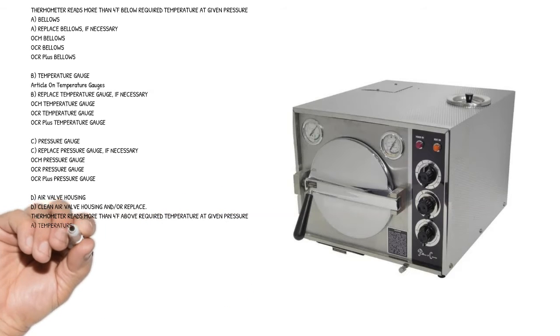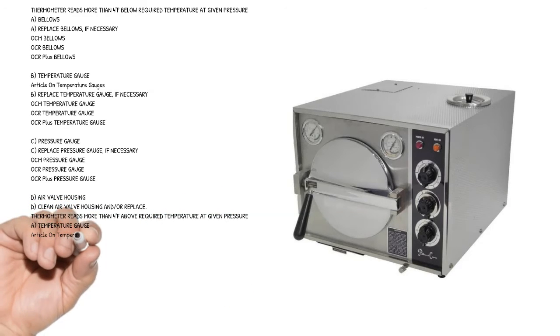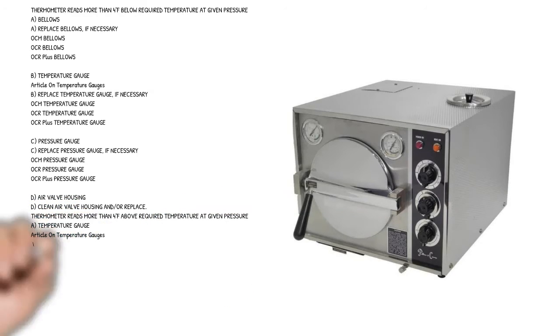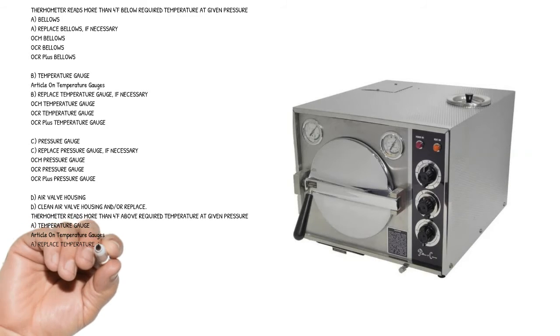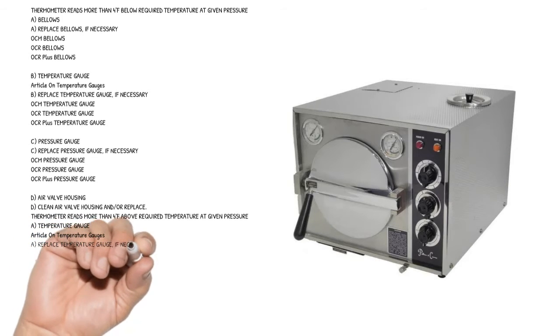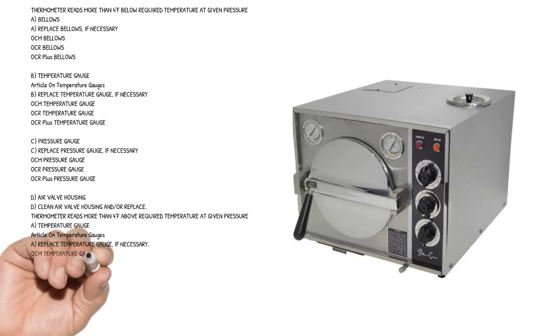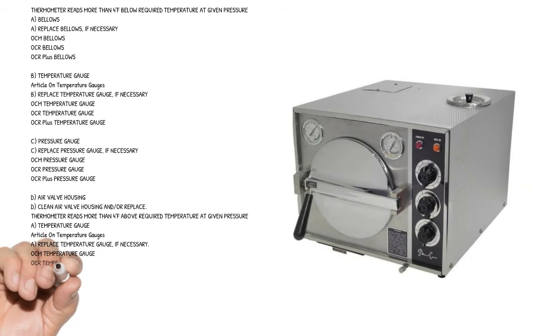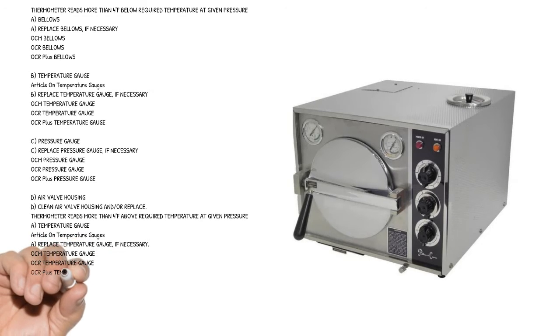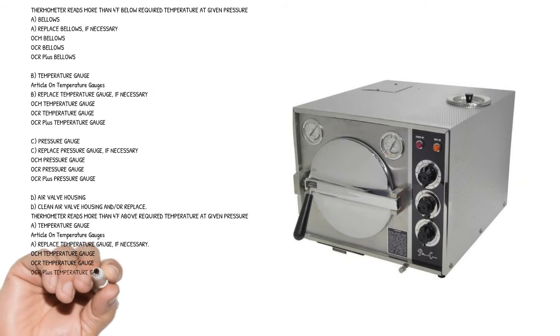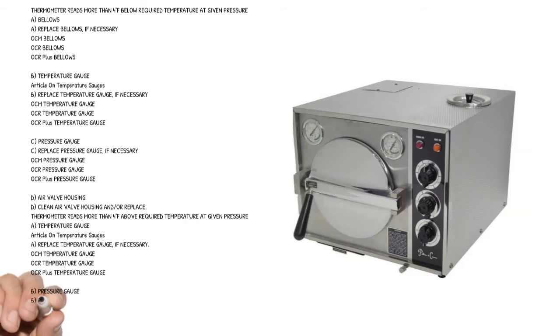Symptom: Thermometer reads more than 4 degrees Fahrenheit above required temperature at given pressure. Cause A: temperature gauge. Article on temperature gauges. Replace temperature gauge if necessary. OCM temperature gauge, OCR temperature gauge, OCR plus temperature gauge.